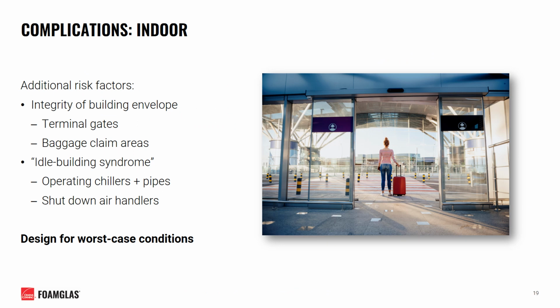Of course, there exist multiple important but less obvious considerations that can often contribute to system failure. For indoor locations, you'll want to consider the environment and any additional risk factors that could contribute to increased humidity exposure. If the integrity of the building envelope is less than ideal, one may need to account for non-conditioned high humidity air coming into contact with chilled water systems. In an airport, this may occur at frequently opening doors, terminal gates, or conveyor openings within baggage claim areas.